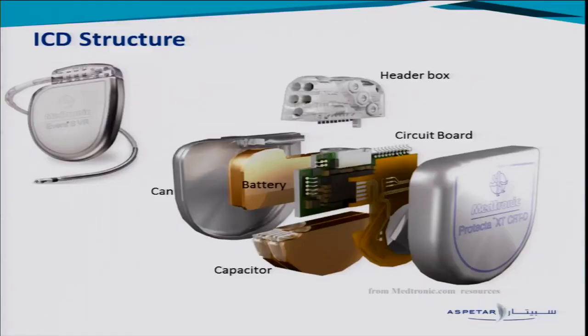What about the structure and function of the ICD? This is an exploded device. Basically it consists of a titanium can. Inside is the battery and the capacitor — the capacitor stores the charge, so when the device charges, the charge is stored here and then discharged to the patient. The battery and the capacitor are the two factors that determine the longevity of the device. This is the circuit board containing all the hardware for programming, and then the header box at the top where the leads are connected — the more leads you have, the bigger the header box.